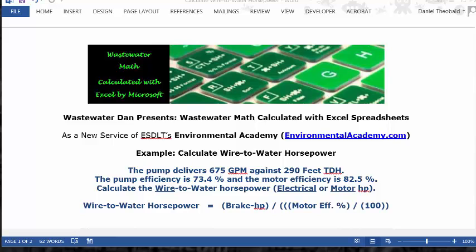Today's solution calculates wire-to-water horsepower with the formula: wire-to-water horsepower equals brake horsepower divided by motor efficiency percentage divided by 100. Motor efficiency percentage divided by 100 can also be described as the decimal equivalent of the motor efficiency percentage.